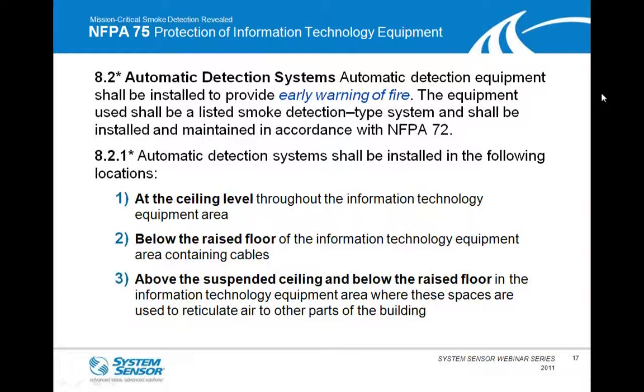So again, if air comes into that information technology equipment area, and then it's going to be filtered in through other parts of the building before returning to the HVAC system, you would need to be above the suspended ceiling and also below the raised floor. Now, there are some discussions currently going on with NFPA 75, some proposed changes, but I'm not going to speculate on those because they're still out for comment.